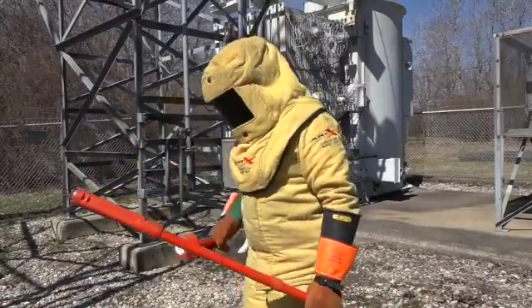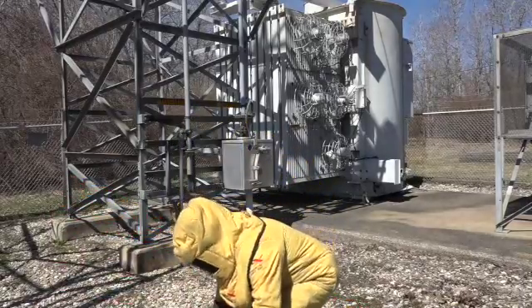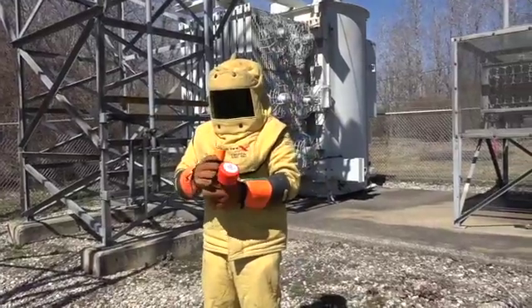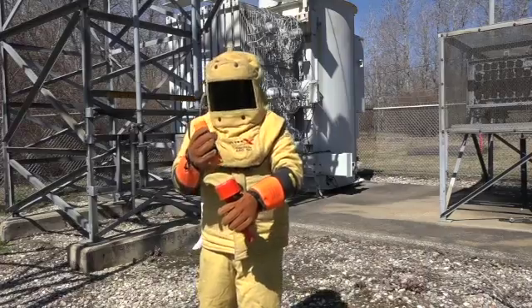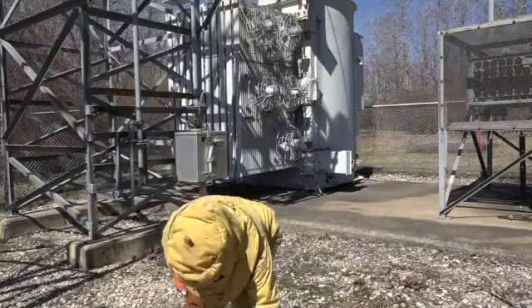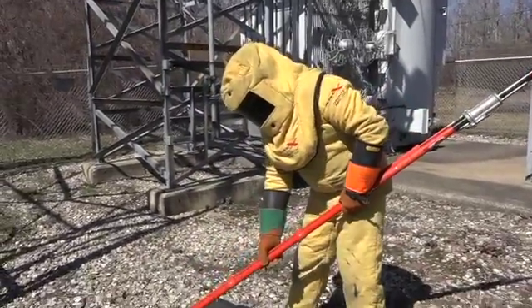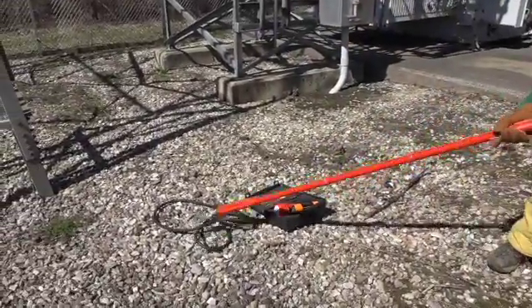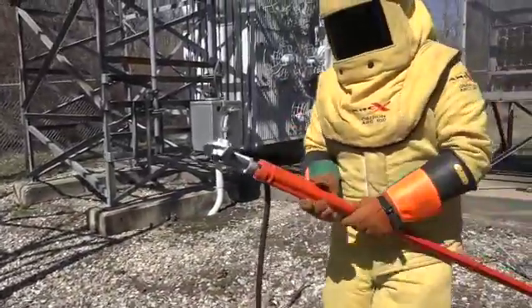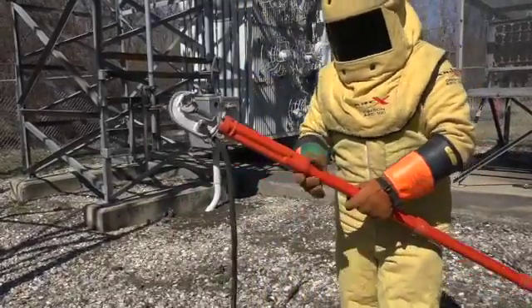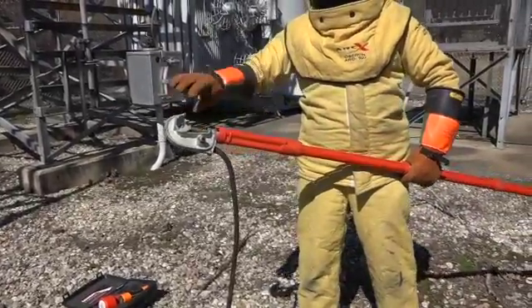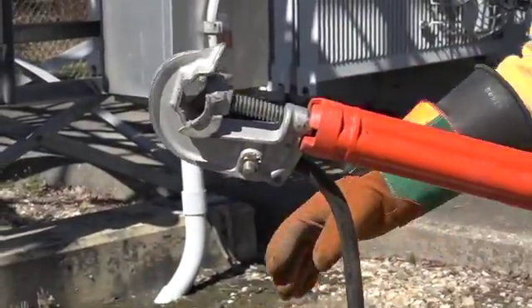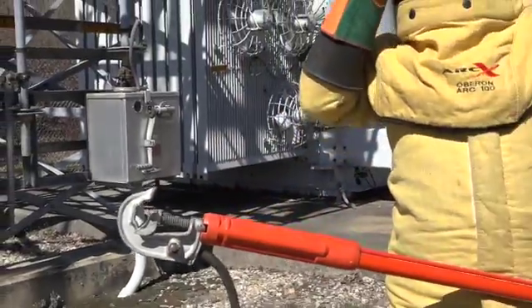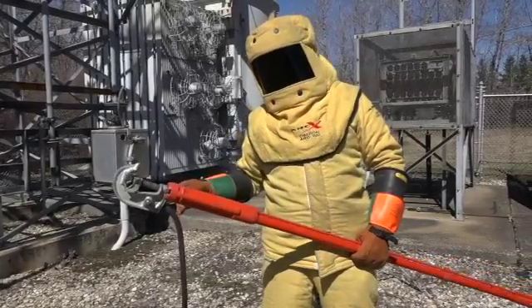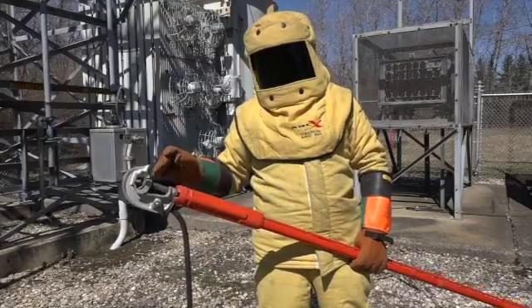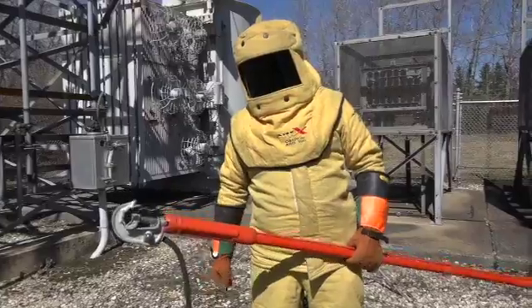Once you prove that the power is off, you retest the tester to make sure it is still working. Then you connect your ground clamp to the end of the hot stick, put it on the wire, and tighten it down. You can turn the hot stick, and there's a screw that tightens down on the wire. The other end of the wire is tied to ground, so that you know there's absolutely no voltage left on the line. These safety practices are critical. They must be followed at all times.